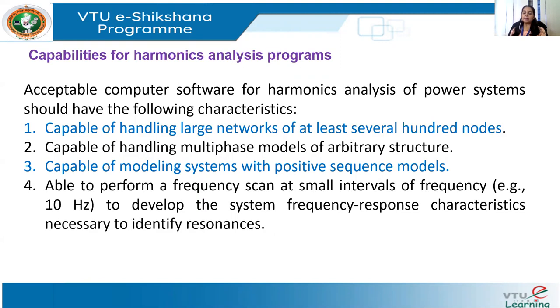Now let us see the main requirements a program should have to analyze harmonics. The first requirement is that it should be capable of handling large networks with at least several hundreds of nodes, because we deal with distribution systems and sometimes need to model very large systems. The computer program should also be capable of handling multi-phase models of any arbitrary structure, since distribution feeders may not always yield balanced positive sequence solutions.